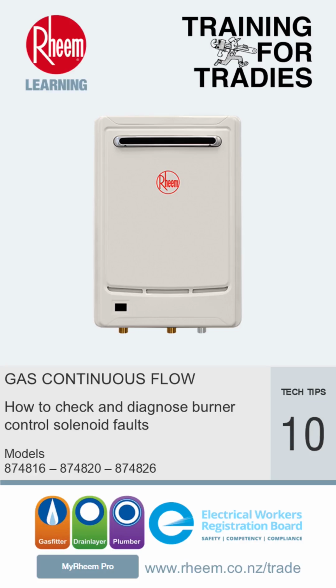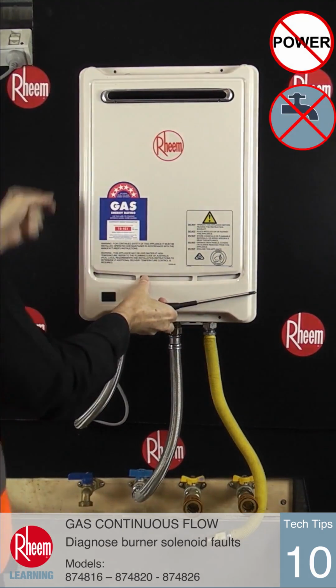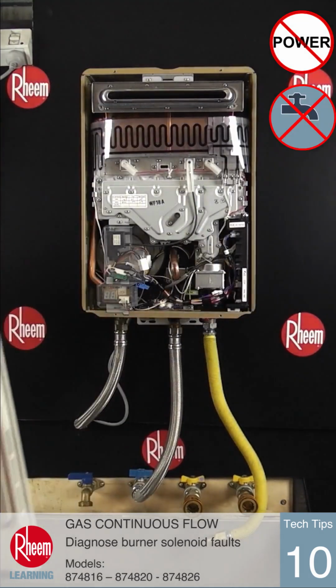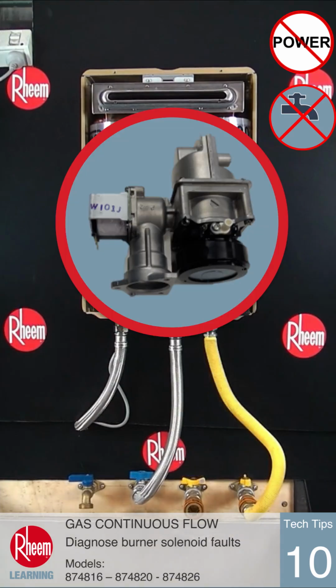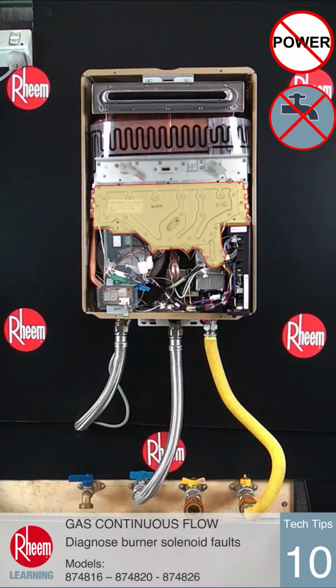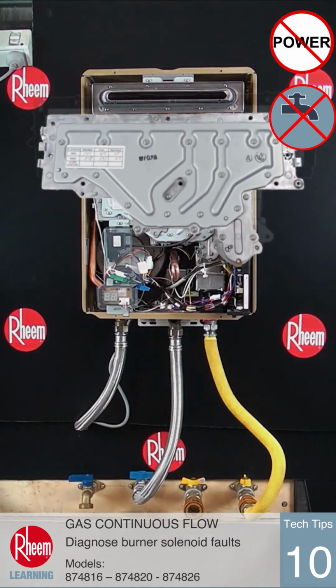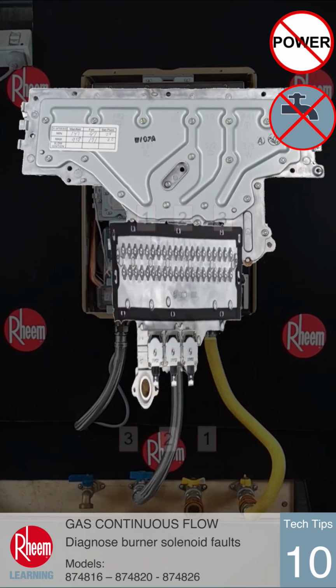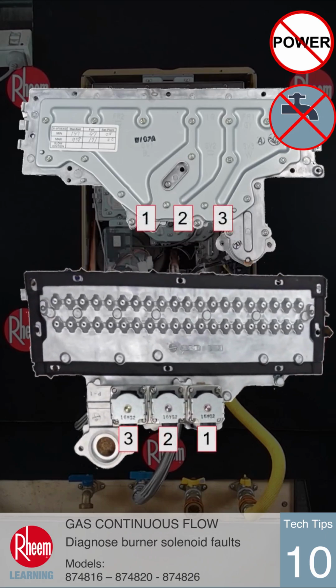This time we're going to show how to check and diagnose burner control solenoid faults on Rheem Series 2 gas continuous flow water heaters. The main gas burner is split into three sections. The inlet gas valve assembly controls gas to all parts of the burner, but there are three separate solenoids located on the lower burner assembly. If any of these fail, the PCB will display error code 11 or 12 during operation.